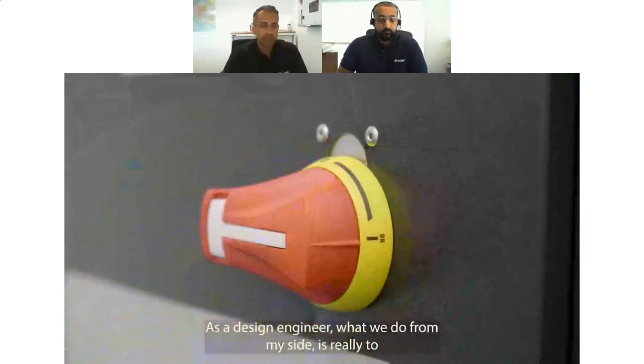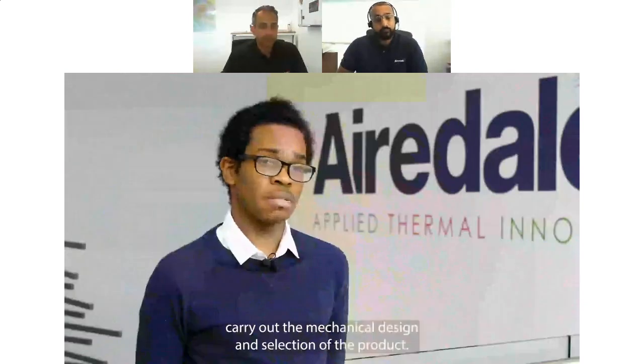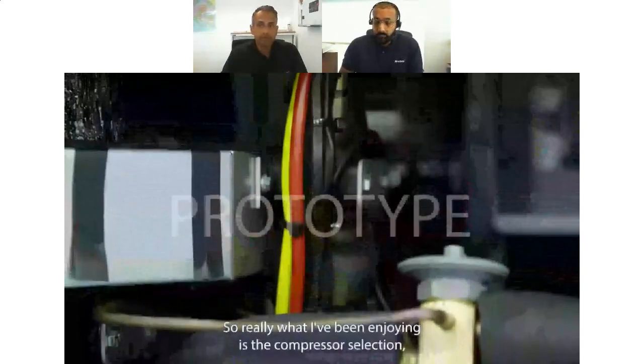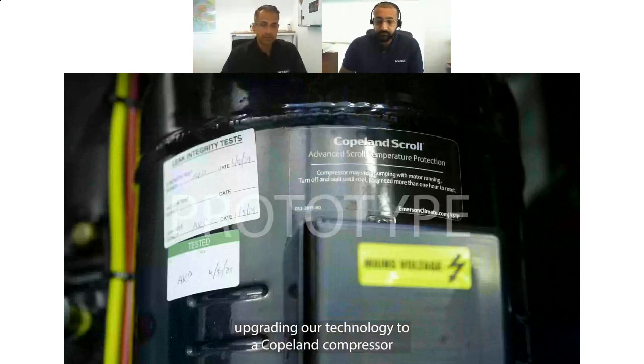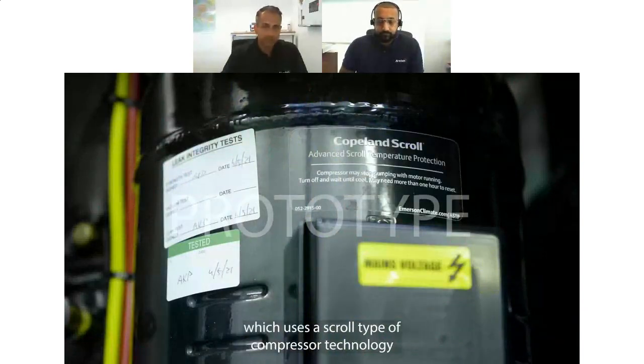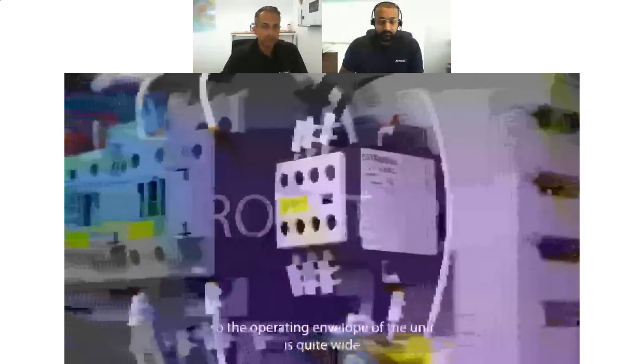As a design engineer, I carry out the mechanical design and selection of the product. I've enjoyed doing the compressor selection, upgrading our technology to the Copeland compressor, which uses scroll type compressor technology. We've done that because it offers full load efficiency gain compared to some other compressor manufacturers, so the operating envelope of the unit is quite wide by virtue of the compressor envelope.